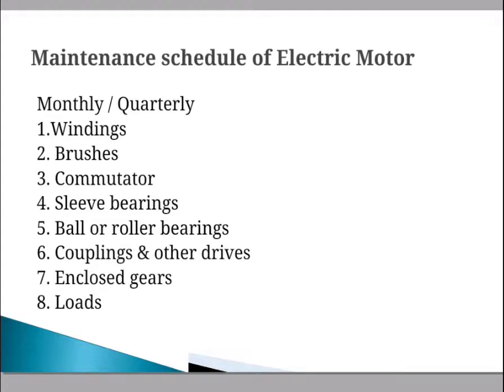Then commutator surface should be examined for high mica, high bar, scratches, or roughness. The commutator surface should be smoothened with the help of emery paper.